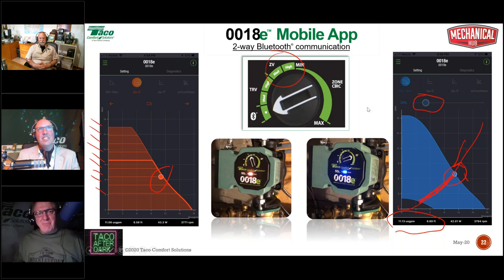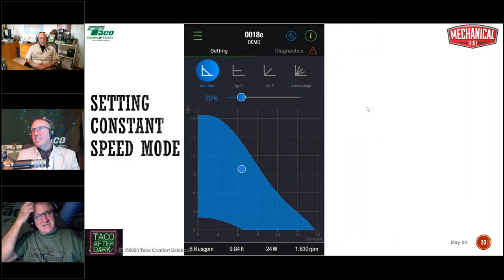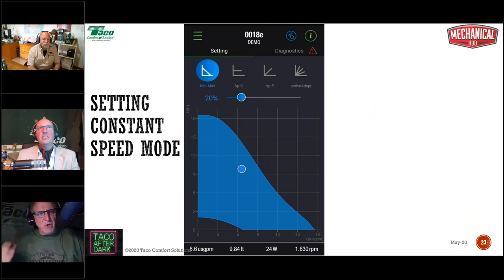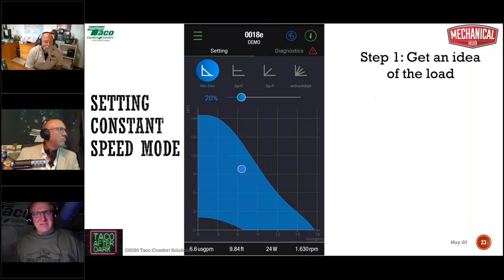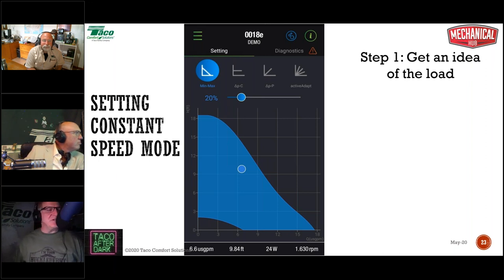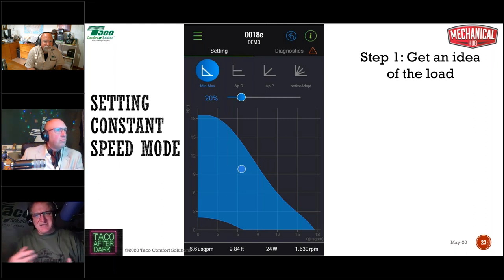So that's what the app will do for you. Now, how to set this up is setting up constant speed mode. First step is to get an idea of the load, whether it's to do a heat loss analysis, or some guys will measure the baseboard and then compare that against the pipe size and see, well, it's got to be about 30,000 BTUs because it's 3/4 inch copper and I got 30,000 BTUs worth of element up there. It's got to be 3 gallons a minute. I mean, it can't be any more than that, that's for sure.